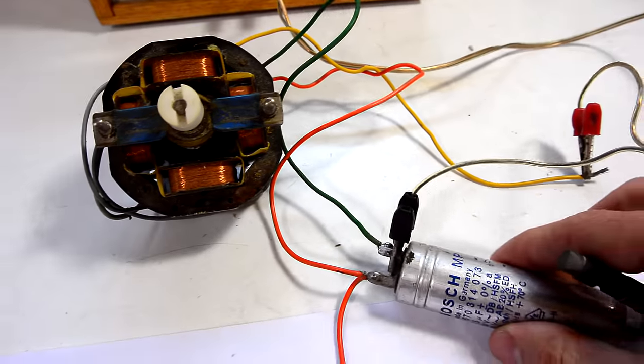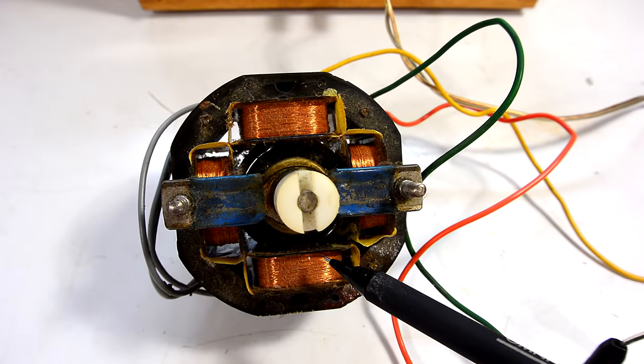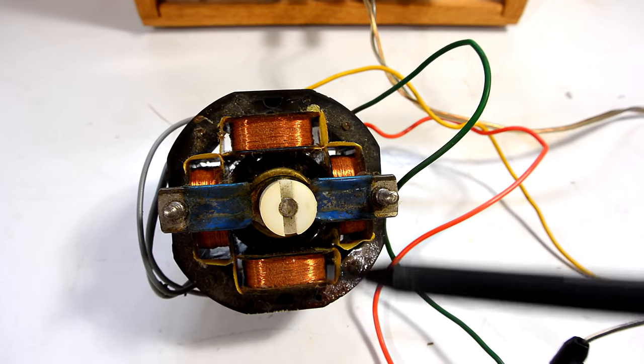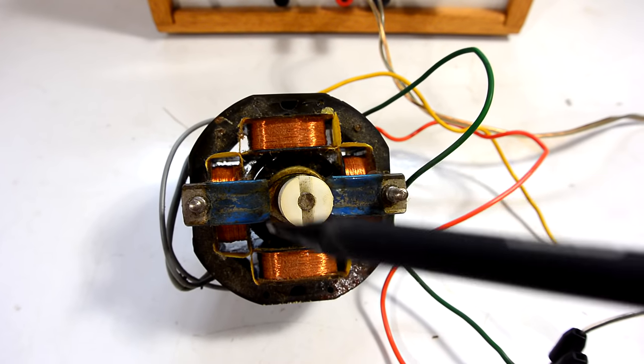The interaction of the inductance of the coils here and the capacitor causes one of the windings to be shifted 90 degrees. So as this one goes up and down and this one goes side to side, they're out of phase 90 degrees so we get a sense of rotation.